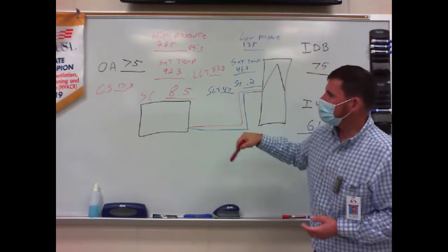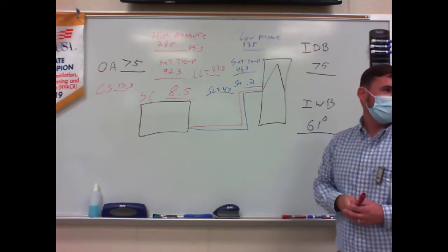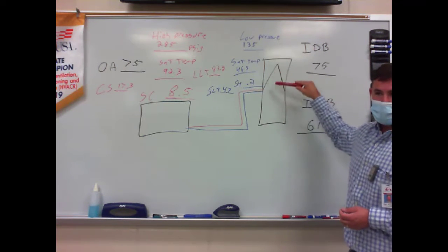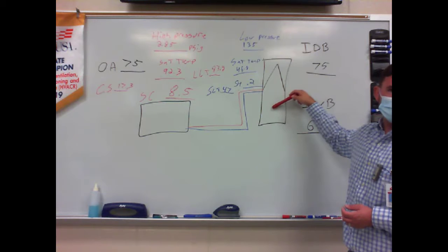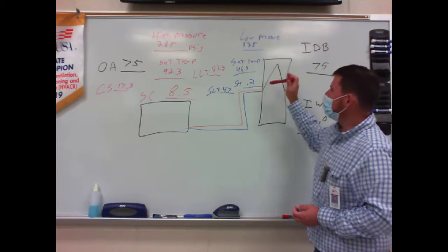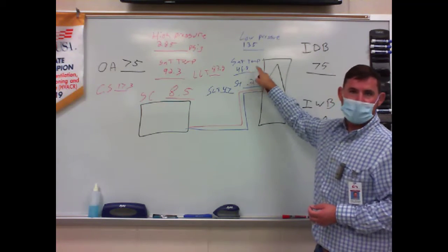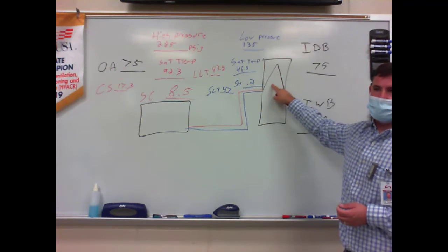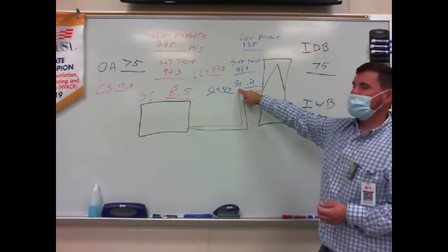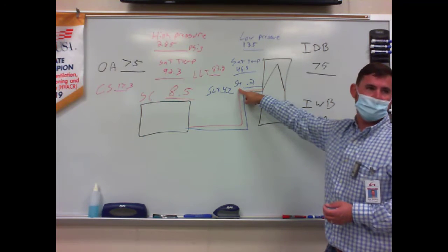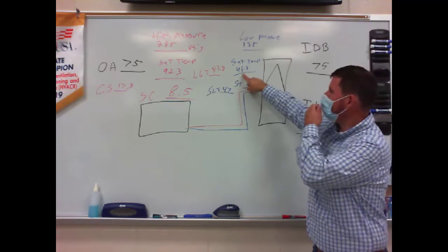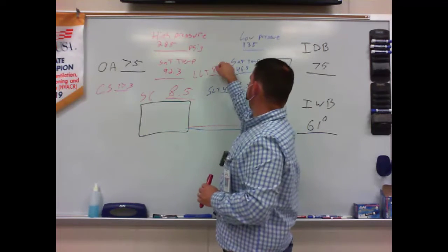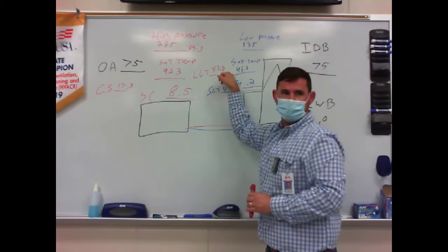But that's something we definitely want to check on that one. So just looking at all these numbers, I can't say that it's undercharged right now. If anything, it looks like I'm either overcharged, I could have a dirty evaporator coil, or I could have low airflow going across it. Typically, you would see that number be lower if I had low airflow or a dirty coil, because I wouldn't be picking up heat. So even though I will be flooded and have very little superheat, if any, 0 degree superheat coming out, normally I wouldn't even be able to pick up enough heat to boil my refrigerant off to get my pressure that high, to have that high of a saturation temperature.